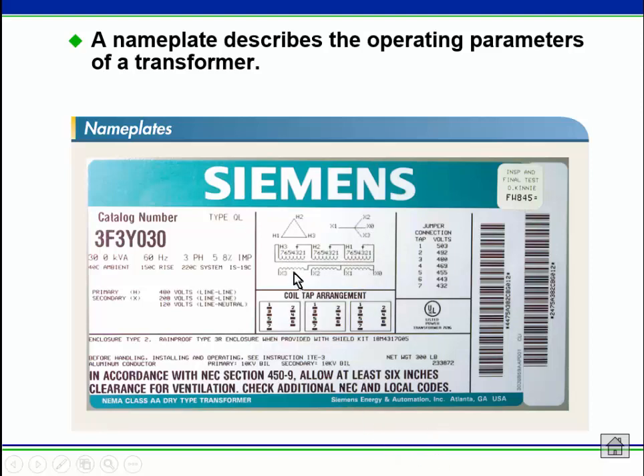There's a diagram that shows the actual connections, and notice the taps. These taps are set up so that if you apply the given voltage at that tap, in this case you will get 208 out, line to line, or line voltage. So essentially what this is doing is tapping the voltage down, right? This is rated 480, 208. So if you apply a higher voltage to it, you'll still get 208. So essentially you have tapped the secondary voltage down by going to tap 1.